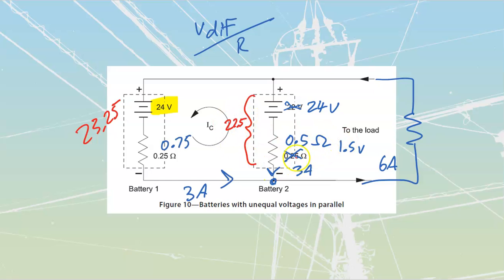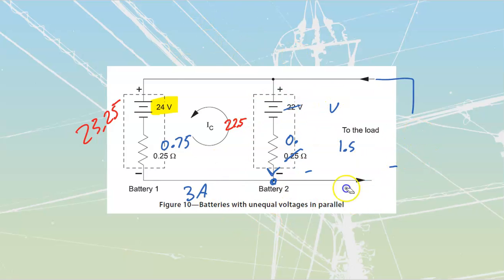So differing percent impedances lead us back to this same original problem, which is that now we have unequal voltages. And as soon as we've got unequal voltages, because the internal impedance of one of these is high enough, it leads to circulating currents between these two as well. I'm not going to draw the circulating current, but it's done the same way: the voltage differential over top of the amount of resistance. So we do need to have the same percent impedances.